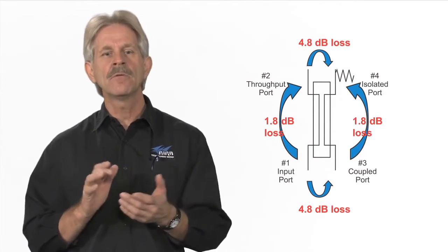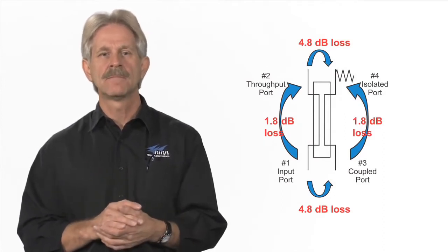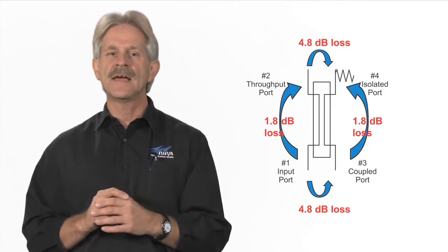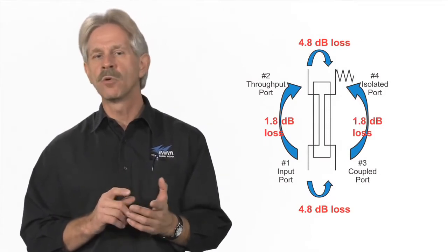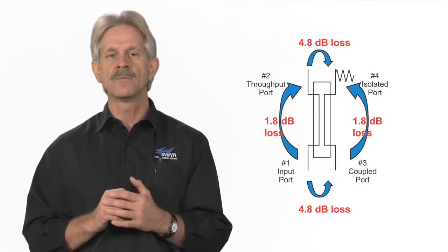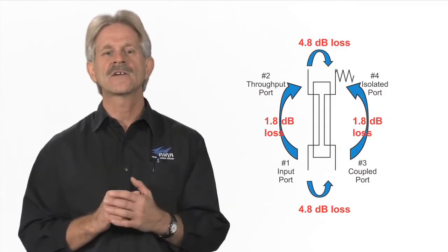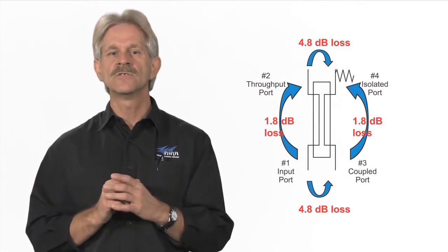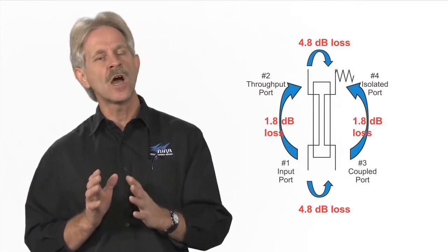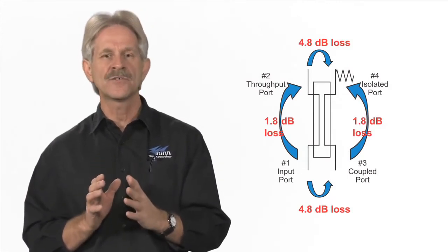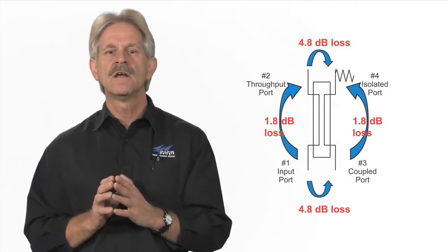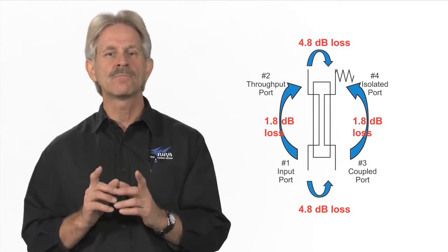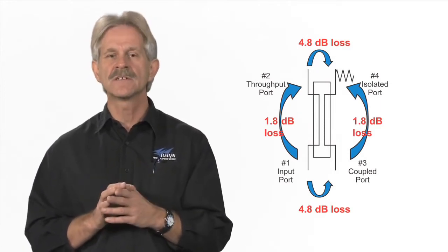An example of one is shown in this image. Using couplers allows a DAS designer to supply a smaller portion of the available signal to a shorter coax branch, but preserve the majority of the RF energy for the longer, higher loss branch. This avoids the need for inline boosters in branches with excessive loss.